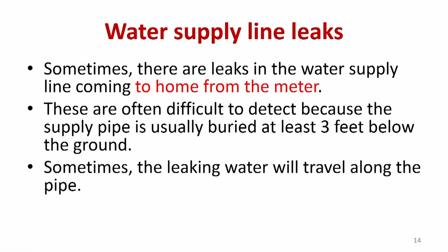And another important thing: your meter reading will be higher because you are not using the water, but it is leaking. These leaks are often difficult to detect because the supply pipeline is buried at least 3 feet below the ground. So you have to tap the ground and you will find some dampness there, and that is the indication of leaking water.